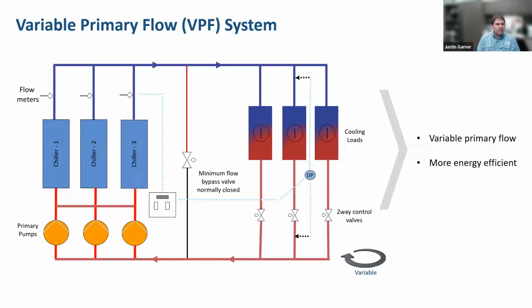And one thing that we see on these systems oftentimes is that the bypass is oversized. So there's a good bit of design consideration that needs to go into these systems to make the bypass work, whereby you still maintain minimum flow on the chillers that are in operation. And there's some pretty standard strategies in the industry to do that. And then obviously you're still controlling your overall pumping to maintain a DP out in the system. You just have to make sure that you don't put your chillers into a low flow condition where they start cycling or surging or going into alarm and things like that. Go ahead and go to the next one, Pete.